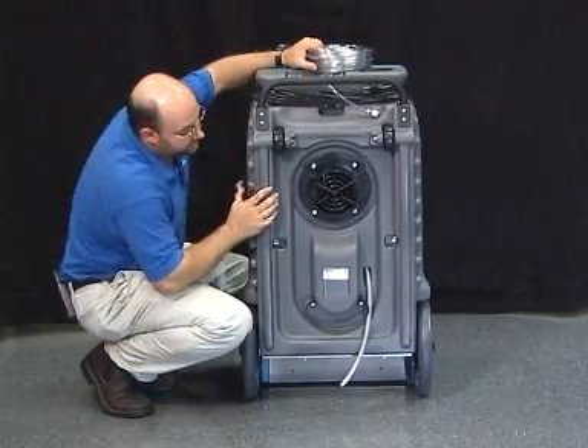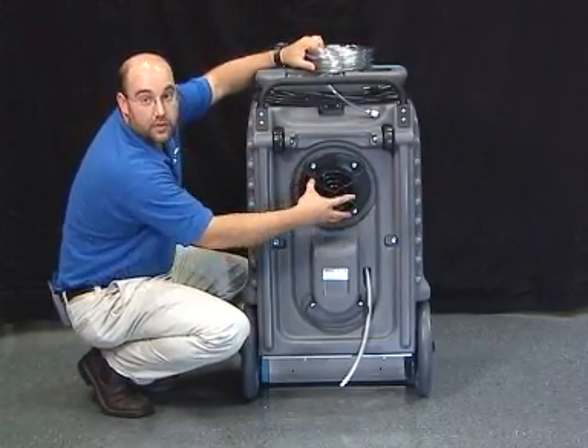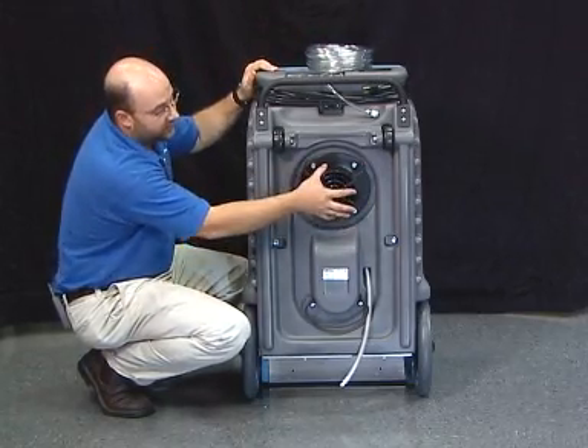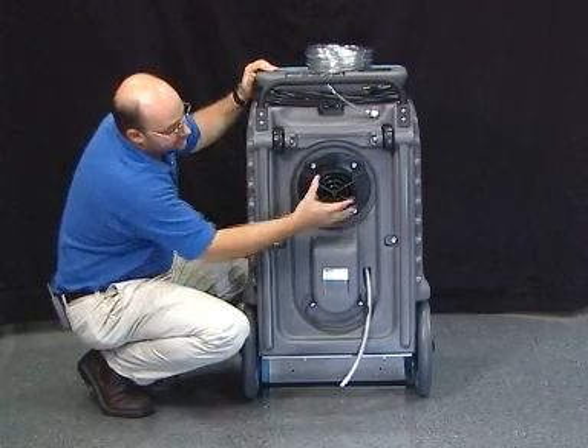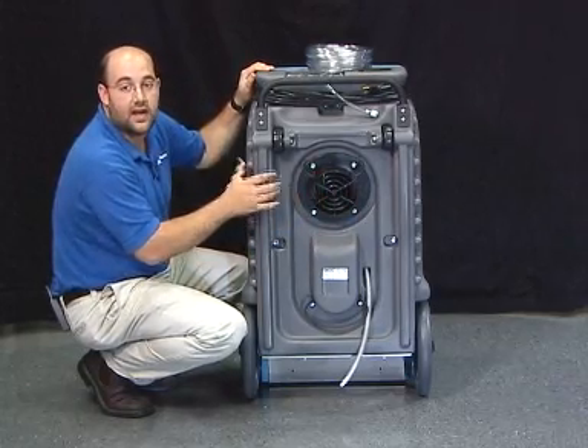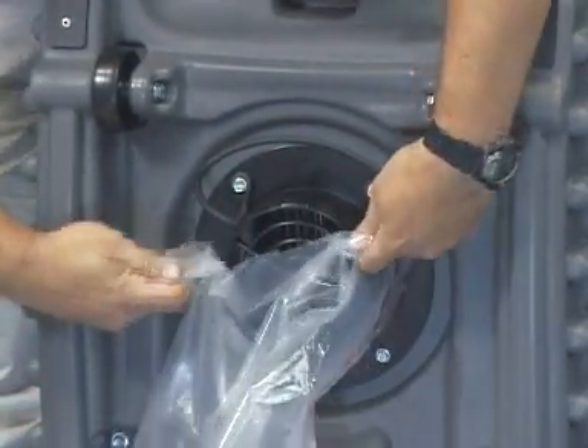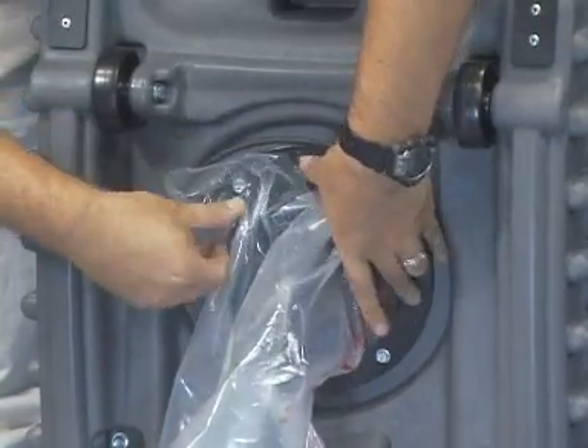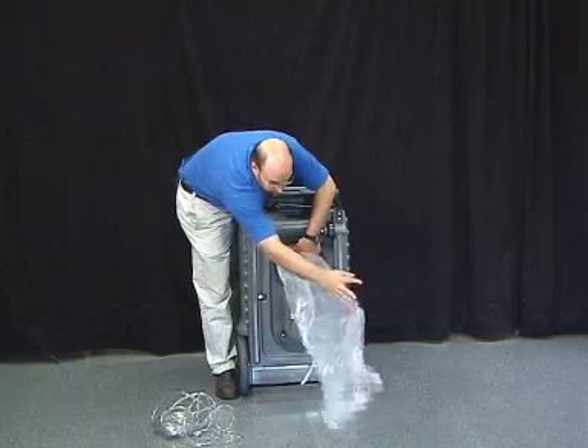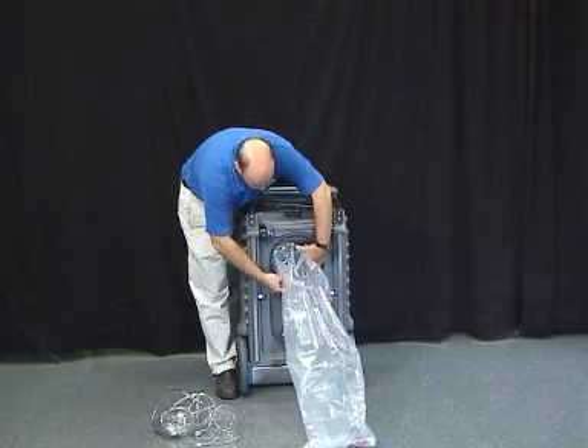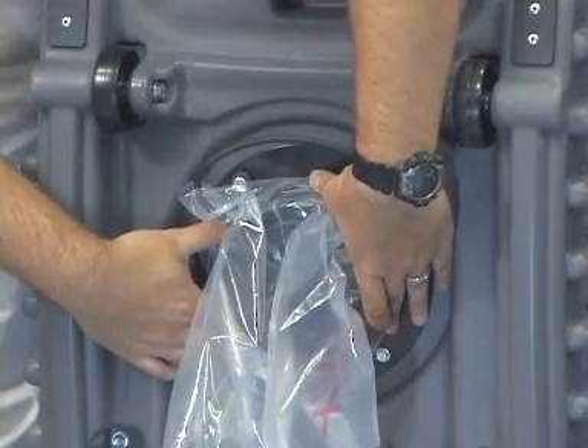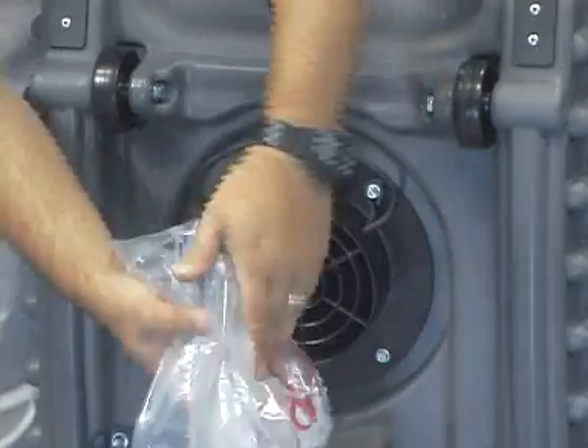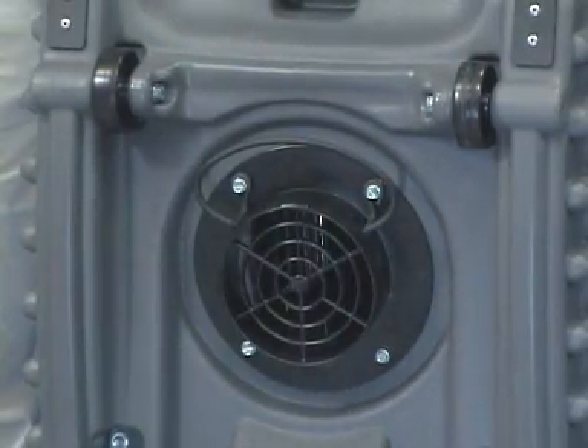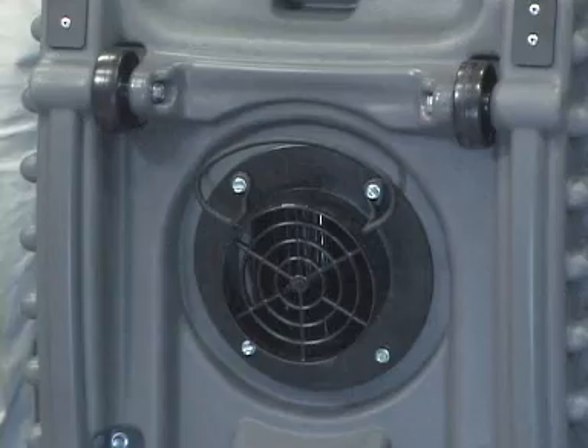On the back of the system, you'll see that there is a collar here. This is where the warm dehumidified air actually escapes or is emitted off the dehumidifier. Another nice feature is you can actually attach ductwork and direct your warm airstream where you may need it to go. With the collar on the back of the system, you can take your lay flat, place it over the collar, and make sure that you fasten it appropriately, whether it be with duct tape or some type of a clamp to secure the ducting. Once the unit is turned on and the airflow is passing through, the duct will be inflated, and it gives you the flexibility of directing that warm dehumidified air wherever you need it to go.